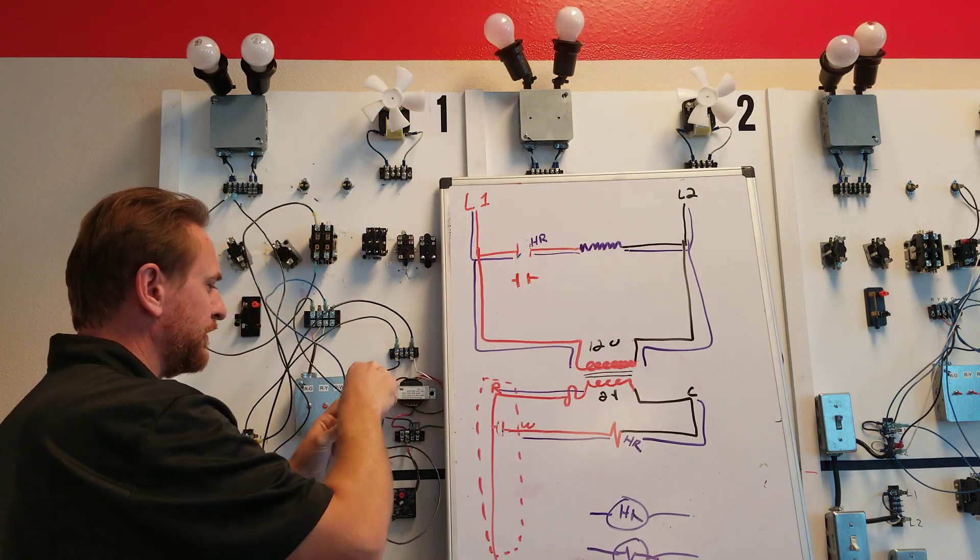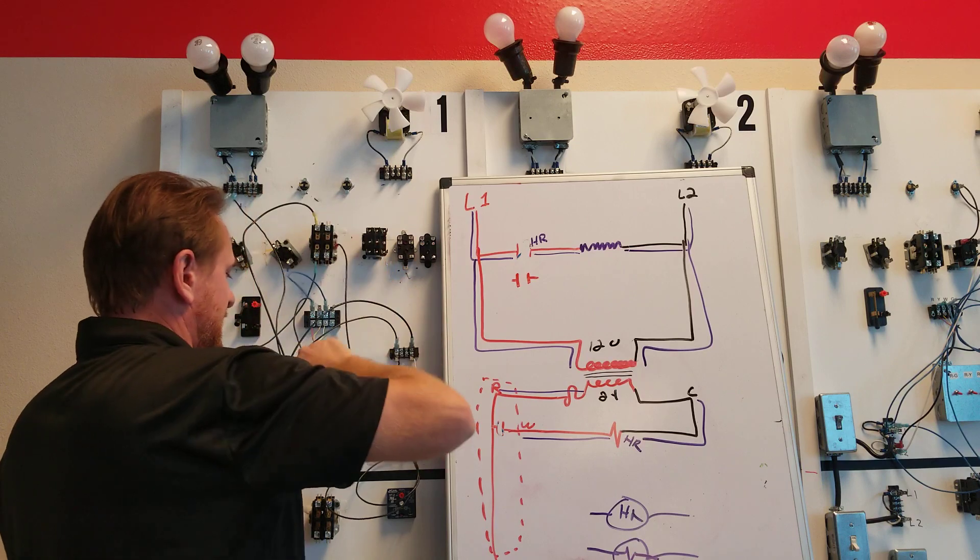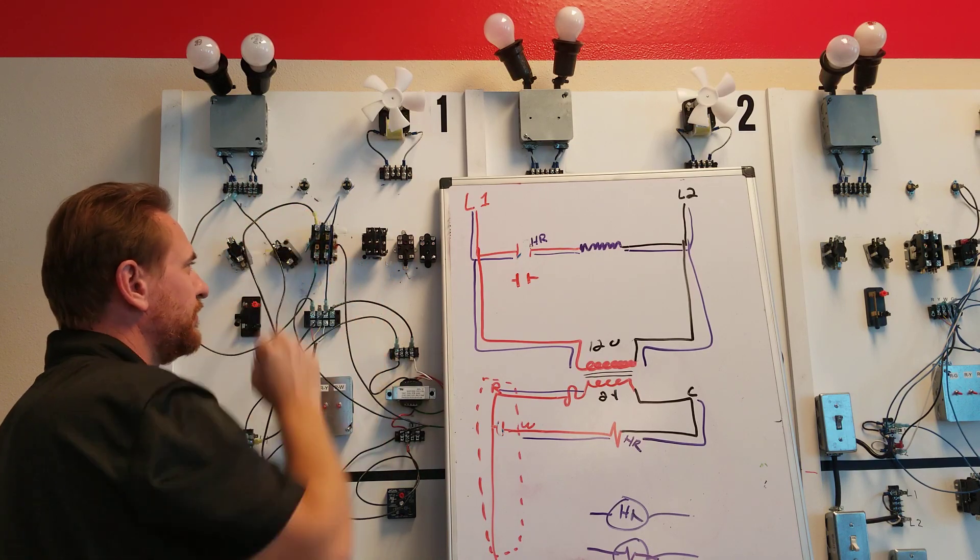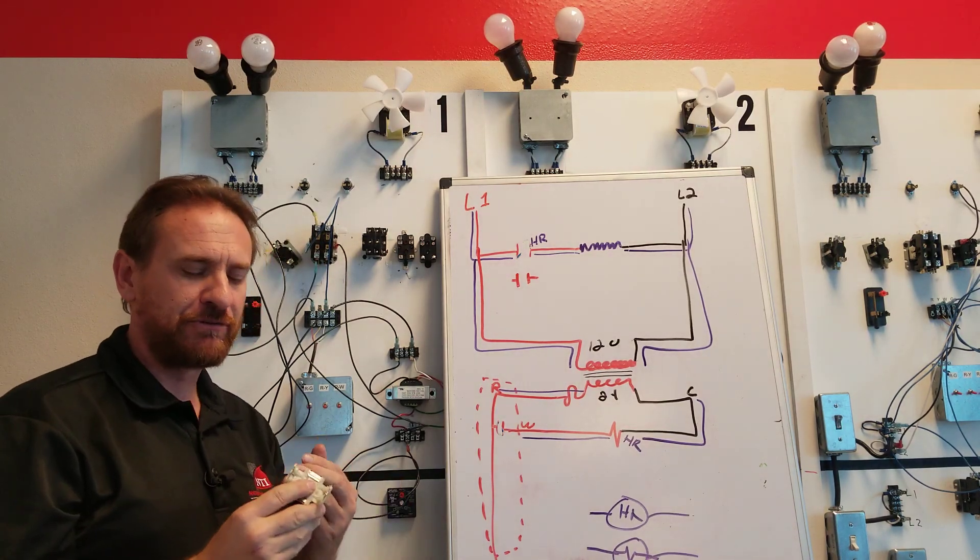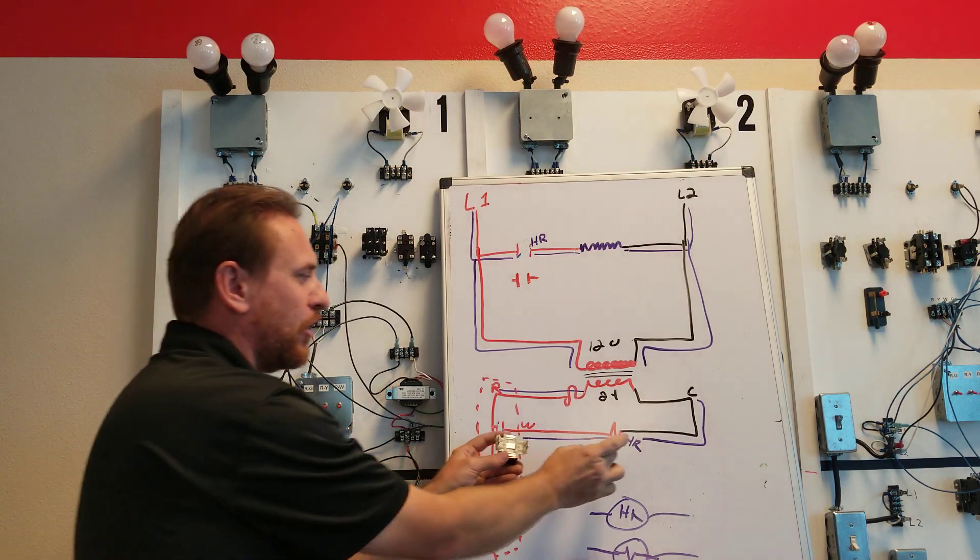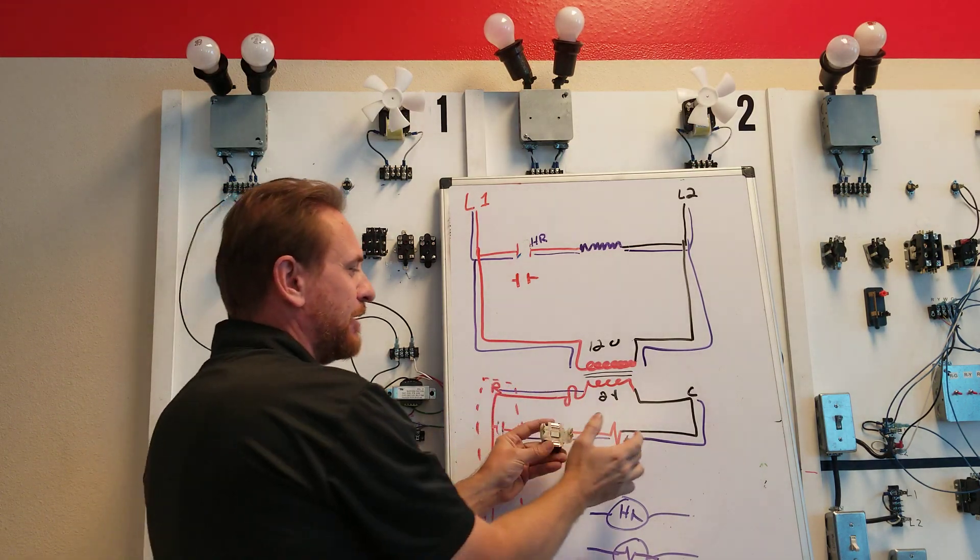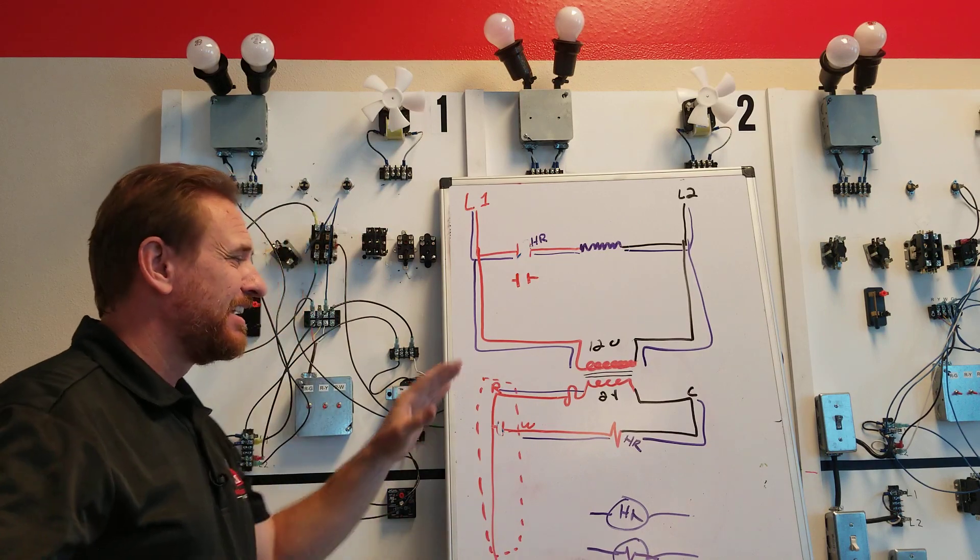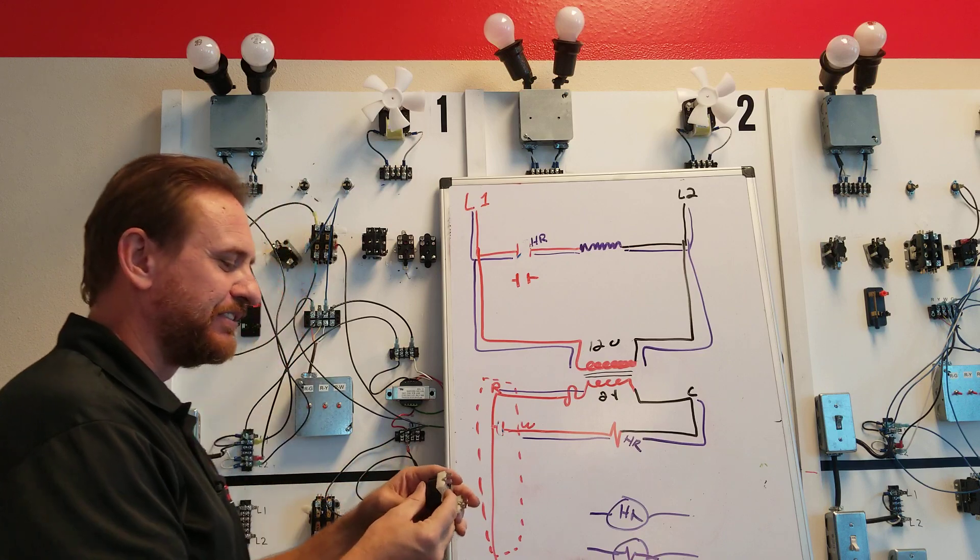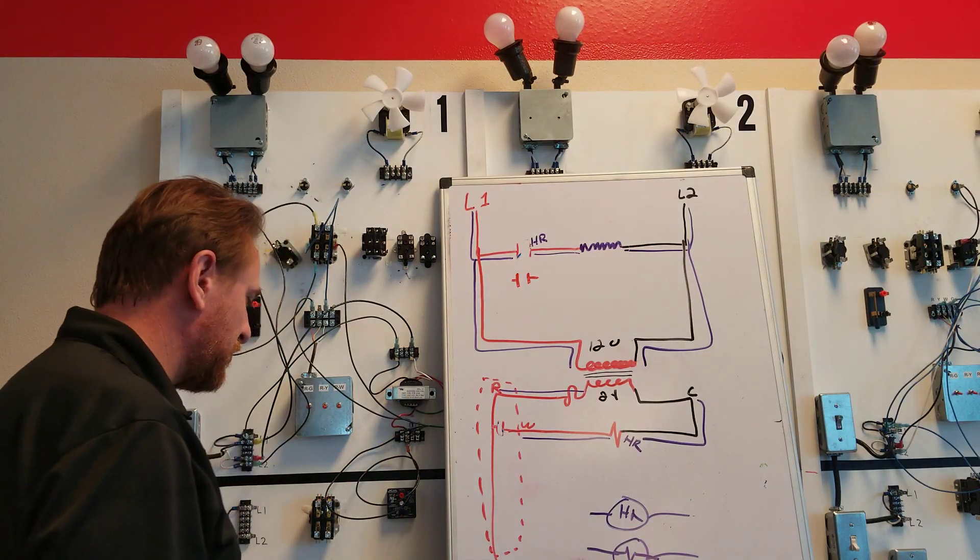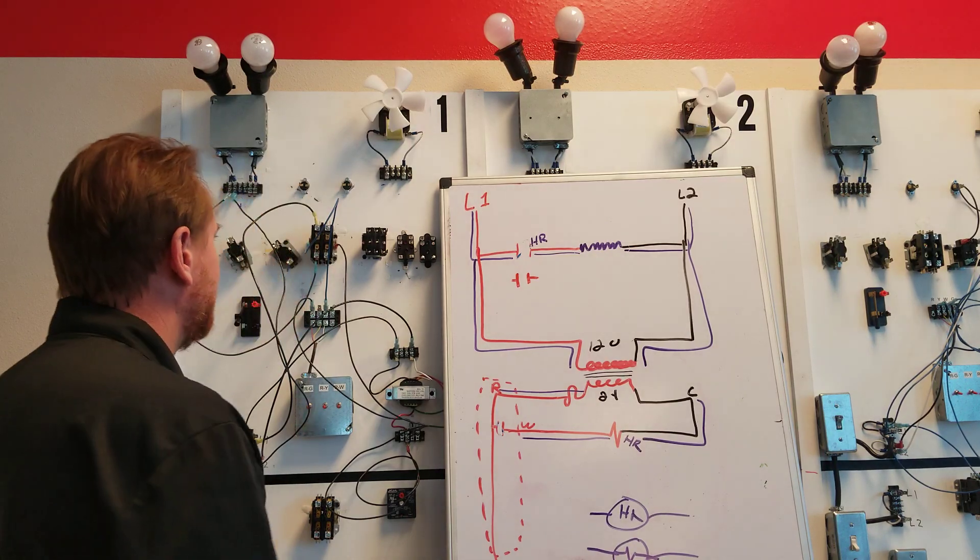So we're going to put this back over here. Not all contactors are 24 volts. For residential they are, for commercial they are not. So you have to read on there to make sure it's the right voltage. I have to make sure that only low voltage goes to the side. If I try to put high voltage here, even by accident because people make mistakes, if we put high voltage on the side of this we're going to have a problem because this is designed for a 24 volt difference.